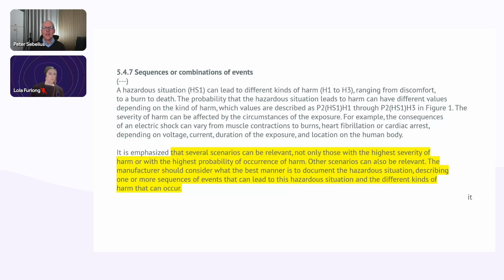I want you to reflect on this because one thing that happens a lot is that people sit and have arguments about this. Like if I were to lock you in a room and say, what's the severity of this electrical shock? And I would lock you in the room for 20 minutes and see if you could agree whether it would be 4 or 5. I bet you would come out and say it's 4.6. And the reason for that is that people are arguing in the risk management workshops. Is it 4? No, it's 5. No, I don't agree. It should be 4. Where in fact, they're just talking about 2 different entries in the risk management table or hazard trace matrix.